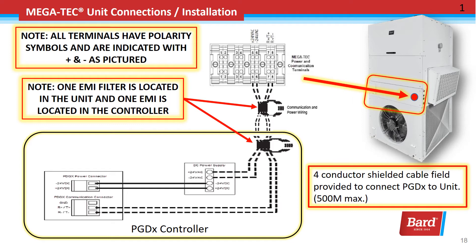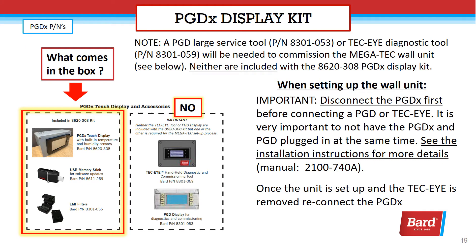One EMI filter is located in the unit and one EMI is located in the controller. Notice that both the power and the communication wire are looped together through the EMI filters. You should note that the four conductor shielded cable is field provided in order to connect the PGDX to the unit. Note that a PGD large service tool or Tech Eye diagnostic tool will be needed to commission the MEGA-TEC wall unit. Neither are included in the 8620-308 PGDX display kit.